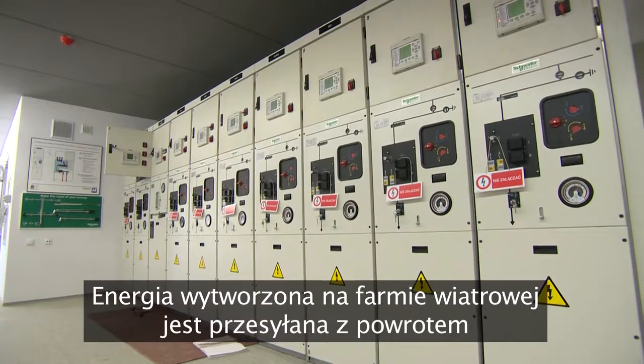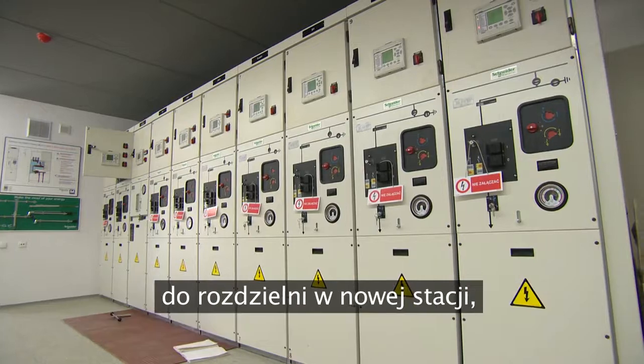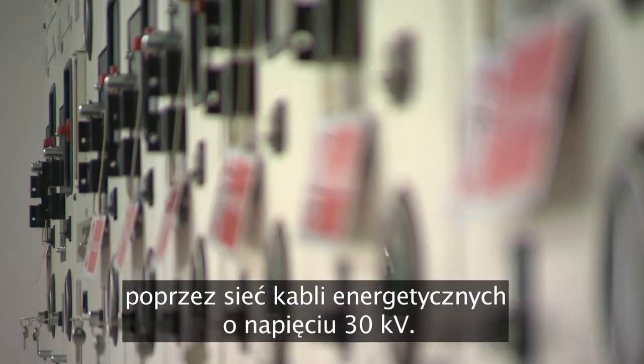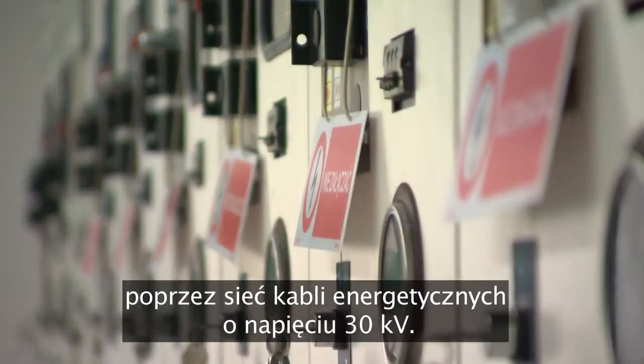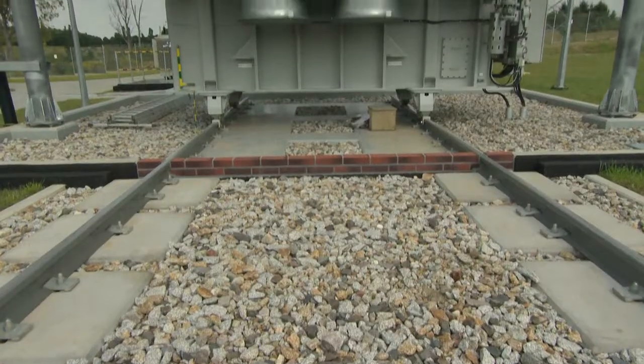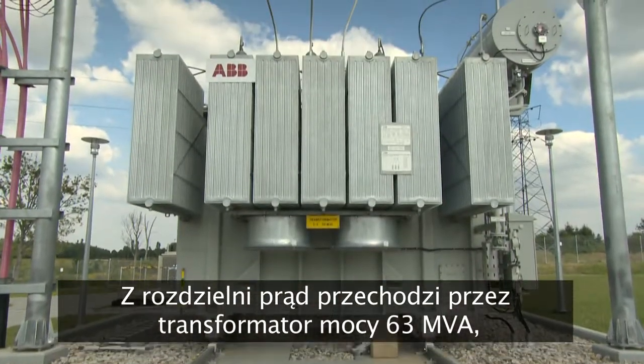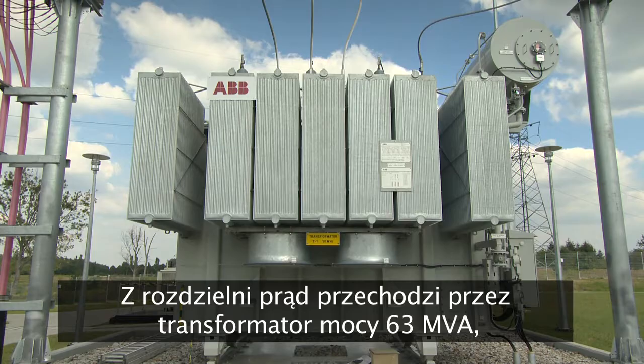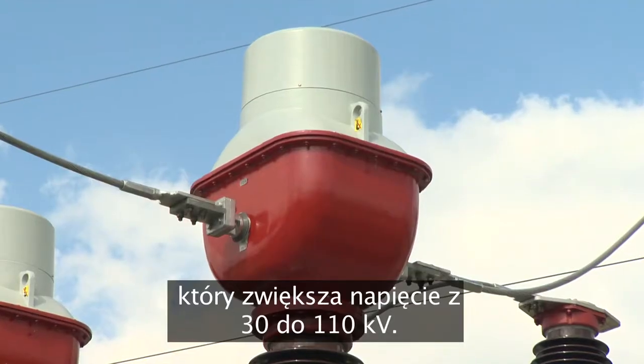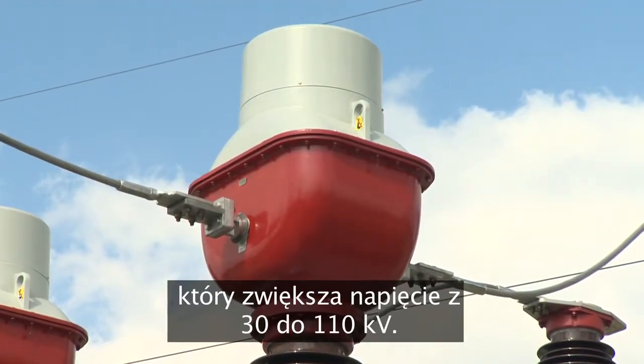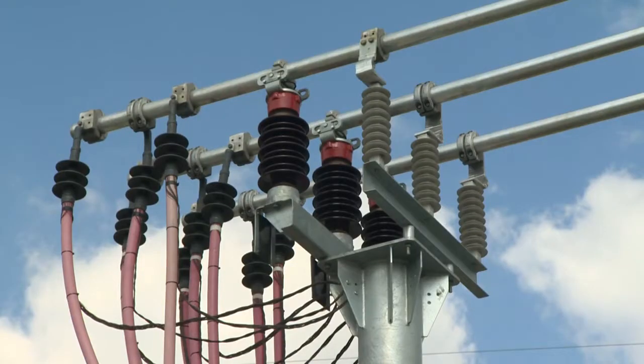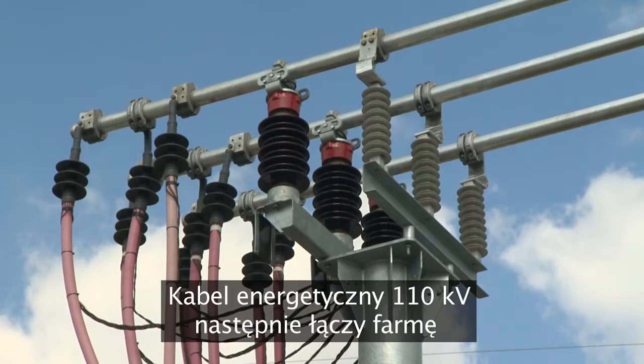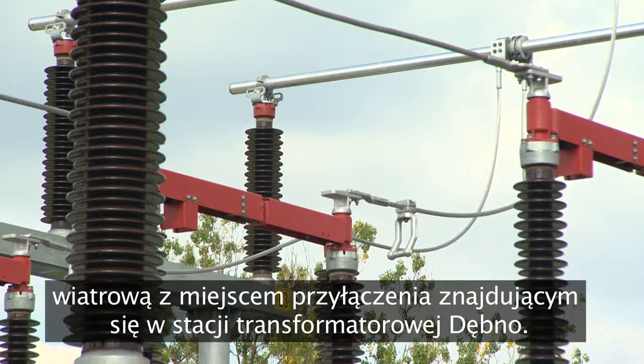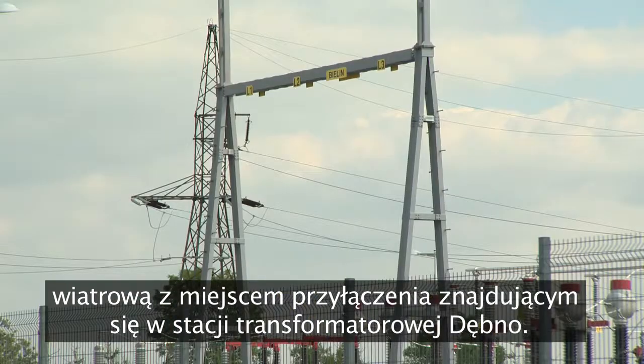The generated power from the wind farm is carried back to the switches within the new substation via a network of 30 kilovolt underground cables. From the switches, the power then goes through a 63 MVA power transformer, which steps up the voltage from 30 to 110 kilovolt. A 110 kilovolt underground cable then connects the wind farm to the point of connection, located within the Debno transformer station.